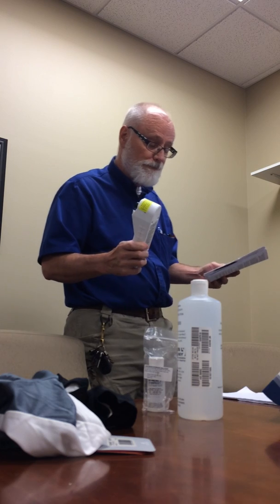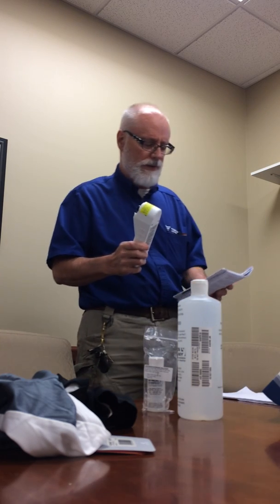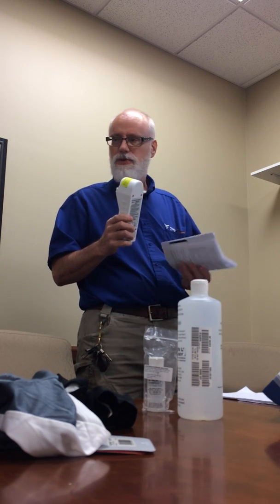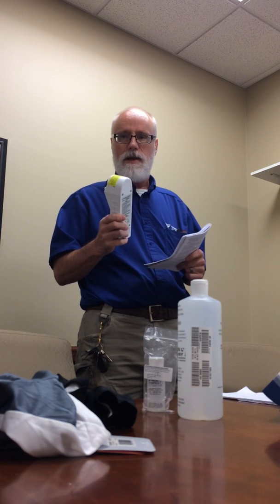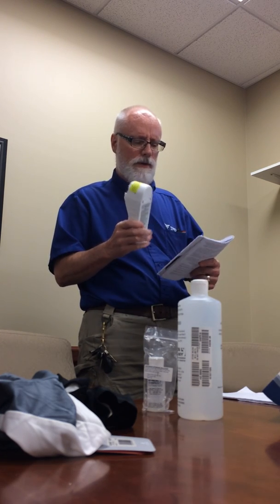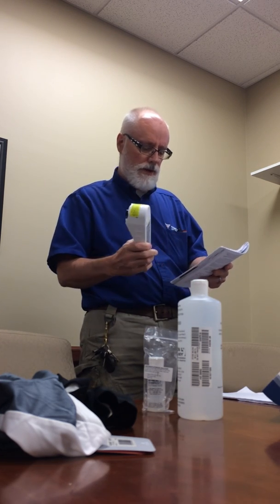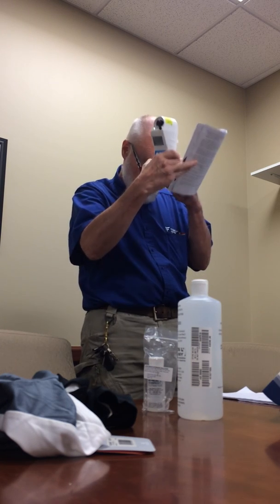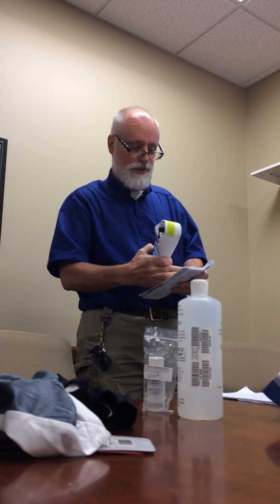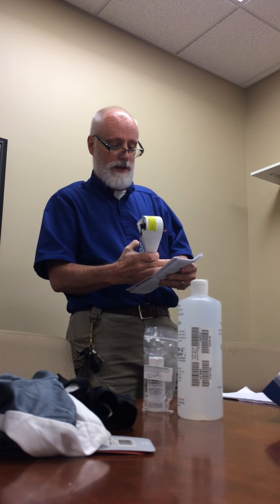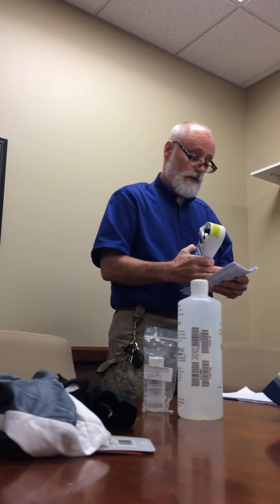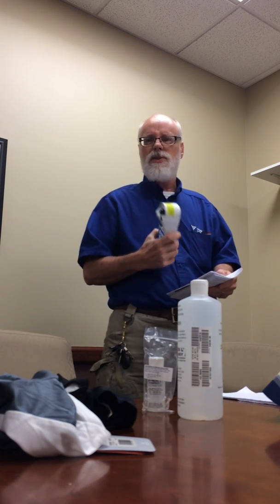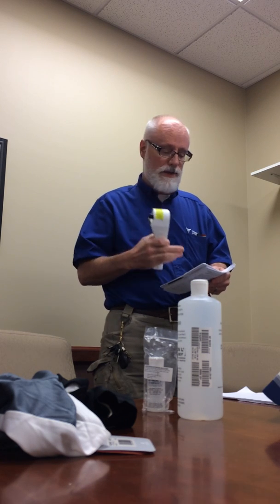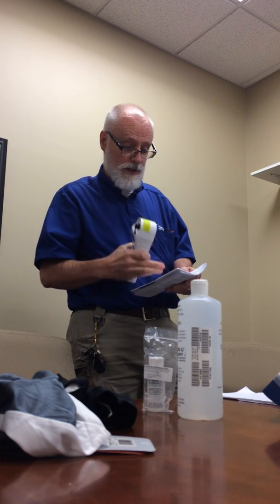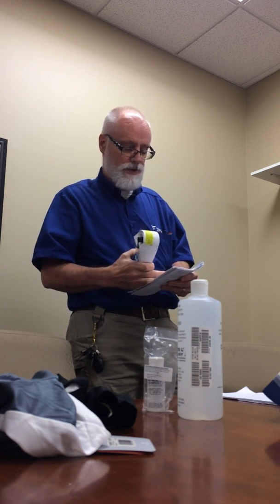If you read the book, it says you should start with the 7 pH. On page 18 there's the range area, it talks about the 14 conductivity and shows the range. We don't use the 7,000 TDS solution, it's listed there but we're not using that. We use the 3,000, and that range is there too.